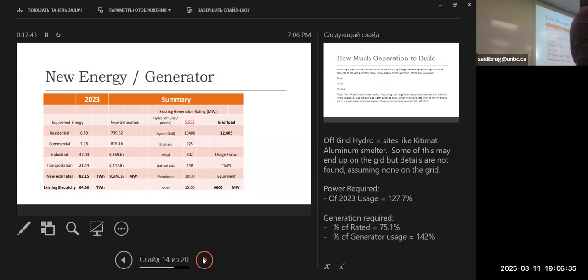And the reason for that is hydro is the big killer. When you look at Site C forecasts, Peace Canyon, most of the ones in the Columbia River, you're seeing usage factors around 53 to 55% throughout the year. That has to do with water levels changing, taking outages — you got to take a dam off, take a power unit offline because you got to cycle the sluice gates for maintenance and check the bearings. So you lose about 60 hours there at least.